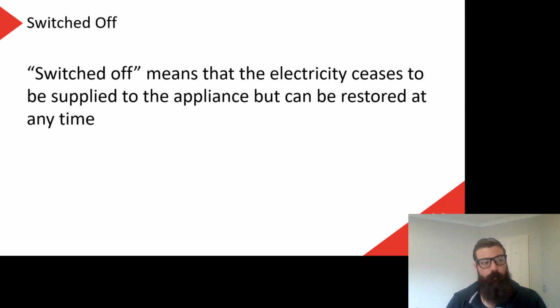which in the vast majority of cases will be physically locking out that circuit like we have discussed before, but it might be other things as well. If there's no ability for us to lock something out, we might physically, after we've switched it off, disconnect the wires coming out of the circuit breaker that go to our circuit, so that even if it was switched back on, that circuit is no longer connected. We've physically taken it out. So that might be another way that we achieve isolation.